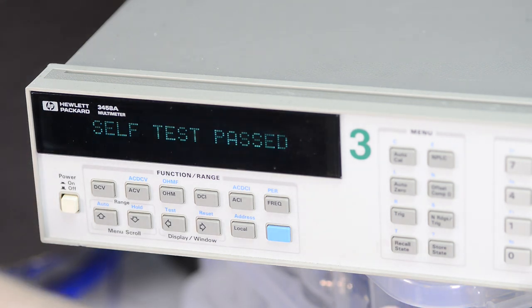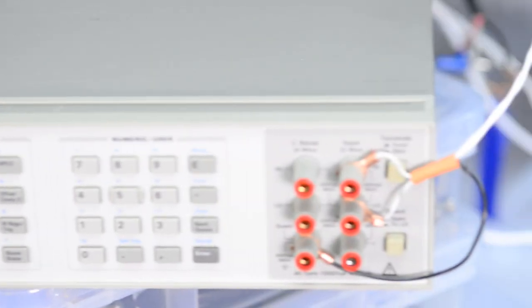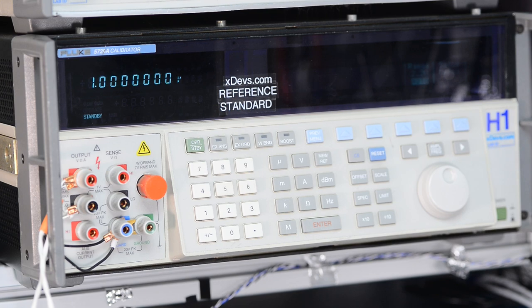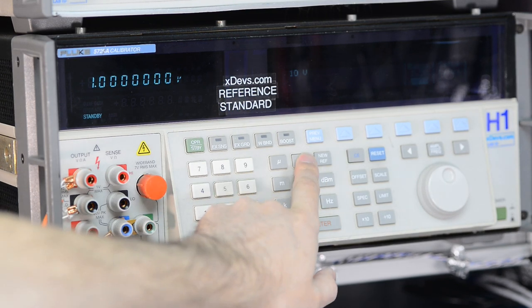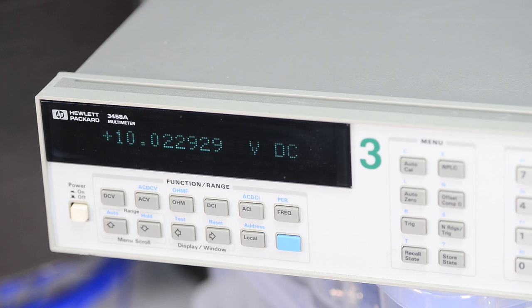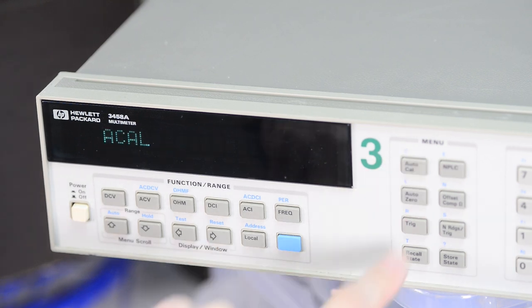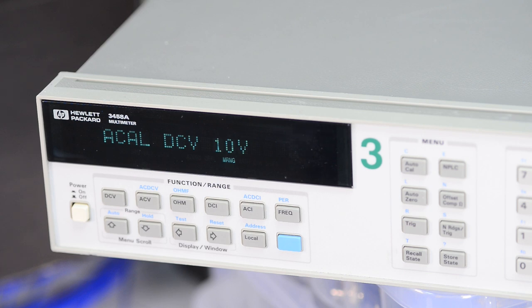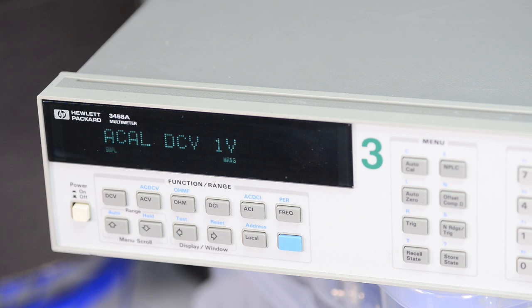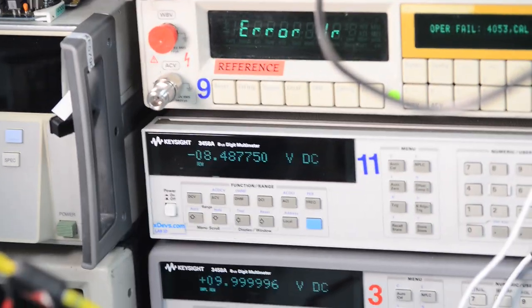So we have self-test pass, a good start, and then we can test with voltage applied to the instrument and see what's going on. For that I use the 5720, so we can configure it to say 10 volts and enable output, and then we should measure around 10 volts. This is what we got on the meter. It looks fairly good, and now we can execute ACAL DCV. This would adjust all the constants to match this A3 board, because it's different from the one originally in this meter. And we should get a voltage closer to 10 volts, because we didn't change the A9 reference.